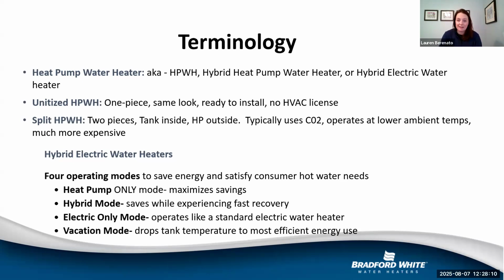That's when you really want to look at the venting options where you can duct out to ambient air outside of the louver door. So we also have split systems. That's a split system heat pump water heater. That's a two-piece system where your tank is inside, but your heat pump water heater is outside. That will typically use CO2 to operate at lower ambient temps. This is much more expensive. This is, I think, where the market will be going, because this is a bit easier to design for. So I think we're going to see a larger increase in manufacturers coming out with their own split system heat pump water heaters.